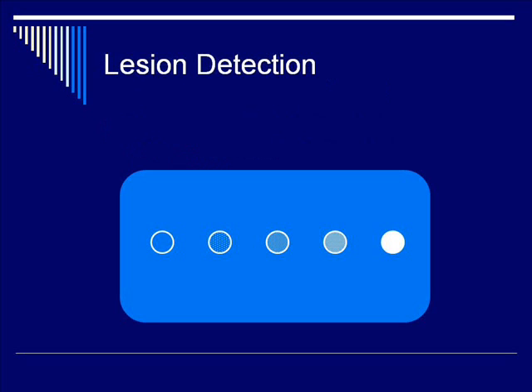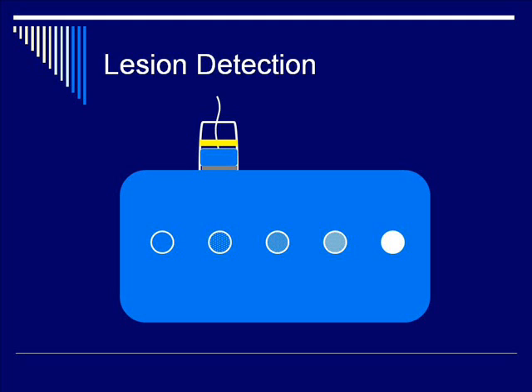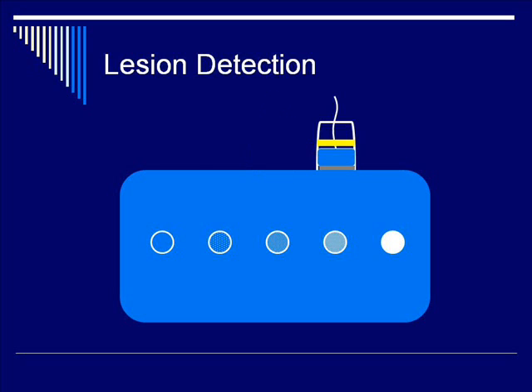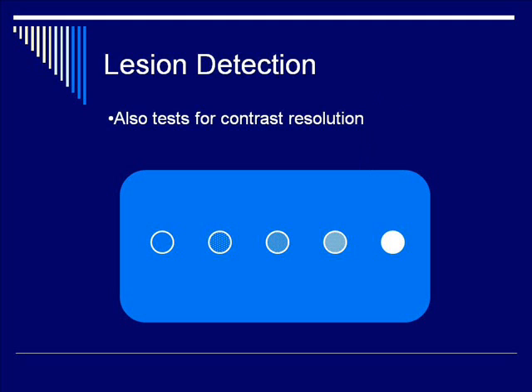The final B-mode phantom to discuss today is a lesion detection phantom. These generally consist of discrete targets of differing sizes, shapes, or echogenicities distributed in typical ultrasound phantom gel. These targets can be hyperechoic, anechoic, or hypoechoic. Because you can resolve these lesions from the rest of the ultrasound gel due to their contrast with the surrounding medium, this is also a type of test for contrast resolution.